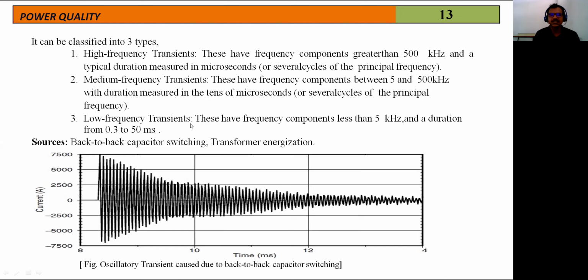Coming to the low frequency transients, the third one. These have frequency components less than 5 kHz and duration from 0.3 to 50 milliseconds. So the frequency is very, very small here, and the duration is very large. The duration of the low frequency transients is higher than that of the high frequency as well as medium frequency transients. The sources of this type of oscillatory transients are back-to-back capacitor switching and transformer energization.